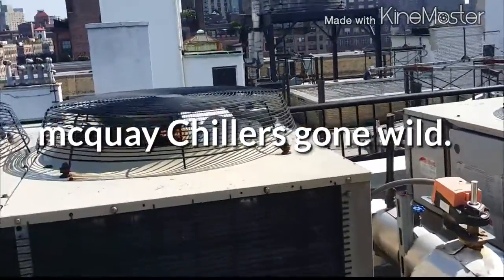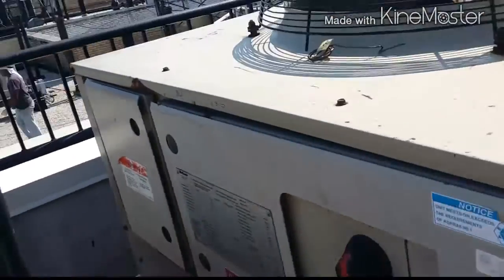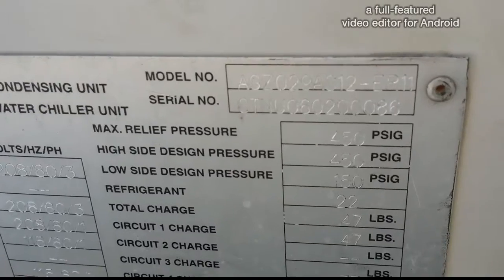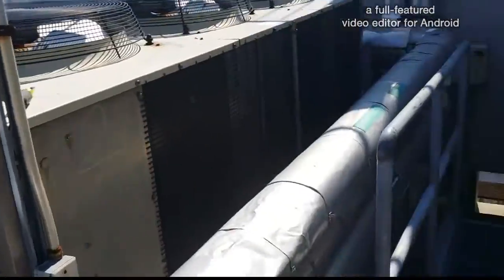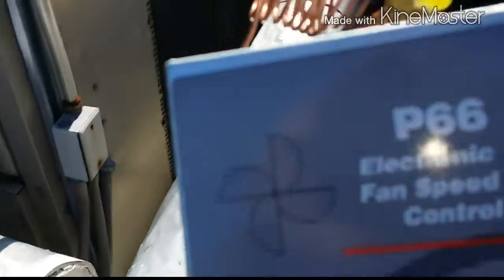Hey guys, Johnny Bag of Donuts here. Today we're going to be working on these air-cooled McQuay chillers — I believe they're 30-ton chillers. We had a problem with one: a flow switch problem. We replaced the flow switch and now that one's running. This one here had a leak on the bellow of the P66 controller, which is this guy right here, so I got the new one here.